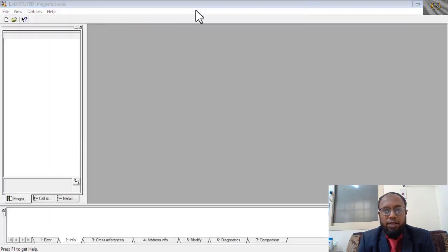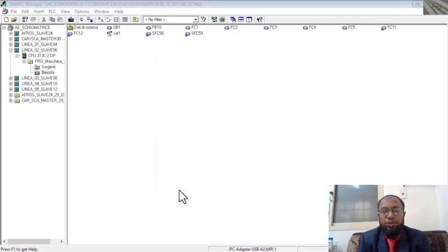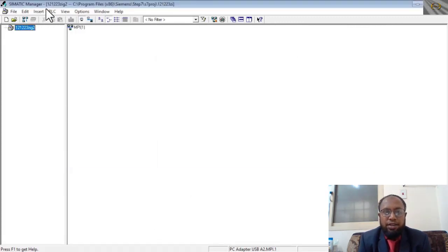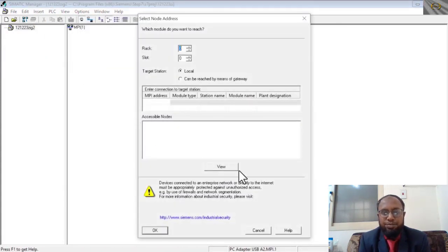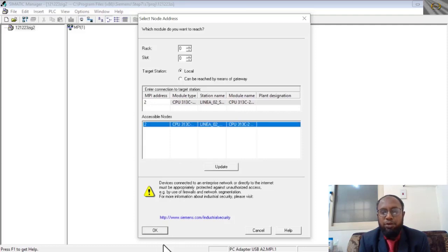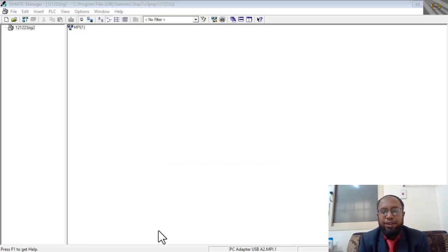Now we are trying to make a new program. Then I will upload the existing program. We got our reference data. Now we are checking from here to upload our new program. Upload destination PG, then find the CPU address by using the MPI A2 cable. Then OK. Now the program is uploading from my PLC.